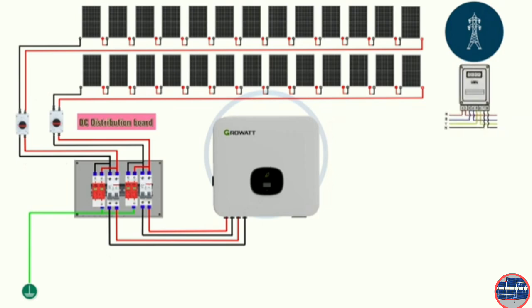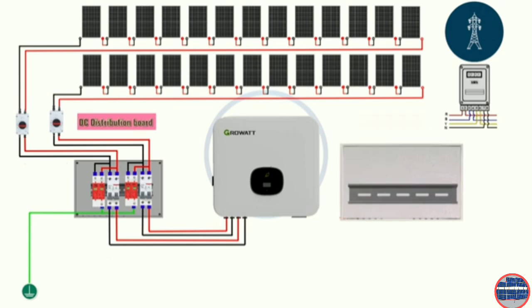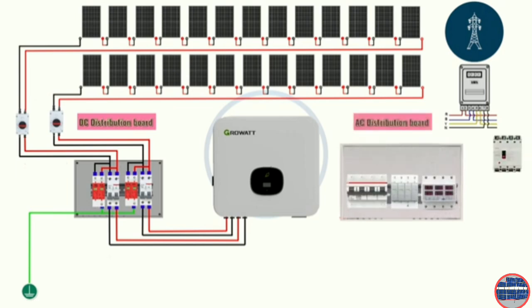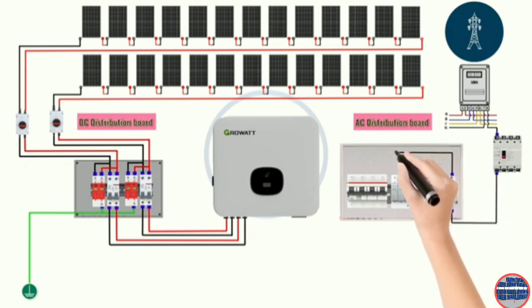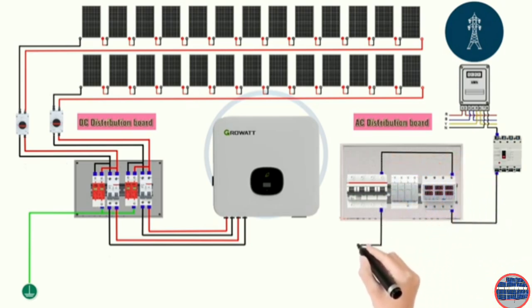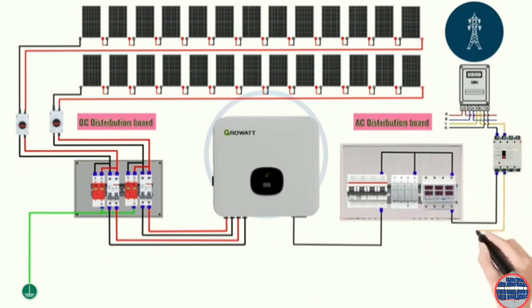Let's take a look at the overall wiring diagram. We'll be connecting our 3-phase grid supply to the energy meter, then to a disconnect switch, voltage protection relay, SPD, MCB, and finally to the inverter. First, we connect the 3 phases RYB or L1, L2, L3 and the neutral N from the grid supply to the input terminals of the energy meter. It's crucial to match the phases correctly. The energy meter measures the electricity consumed.